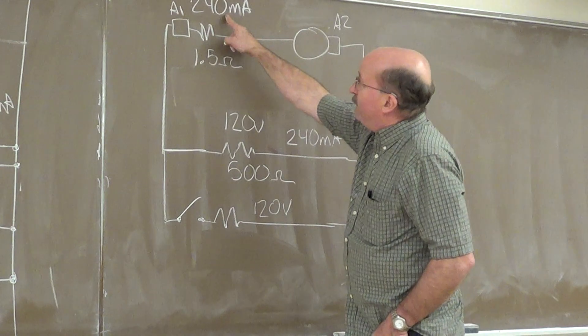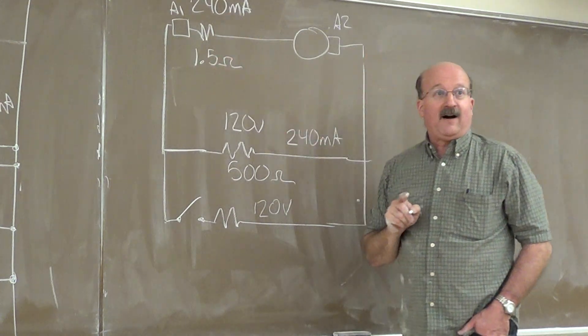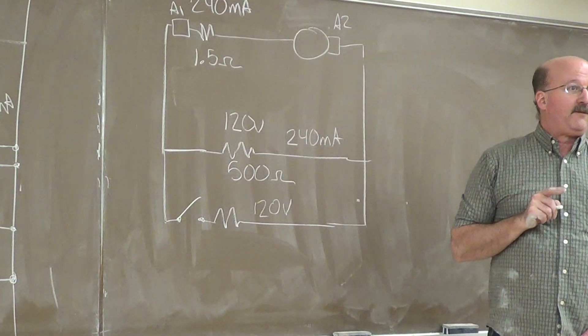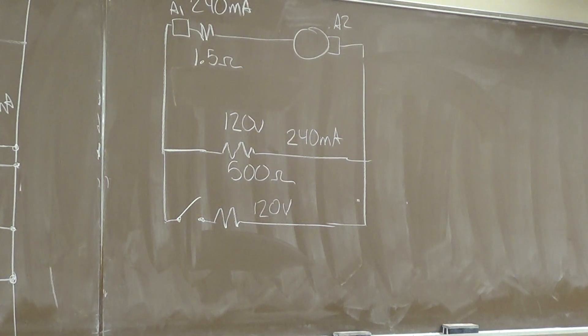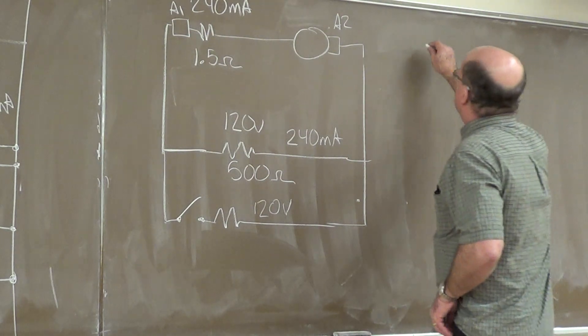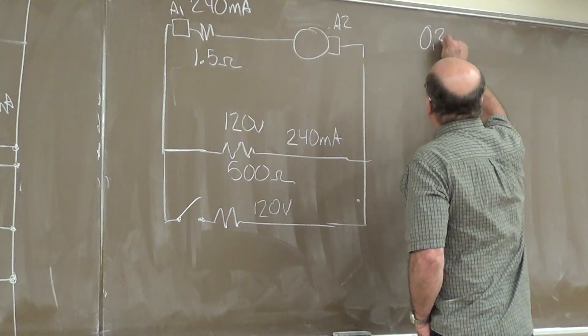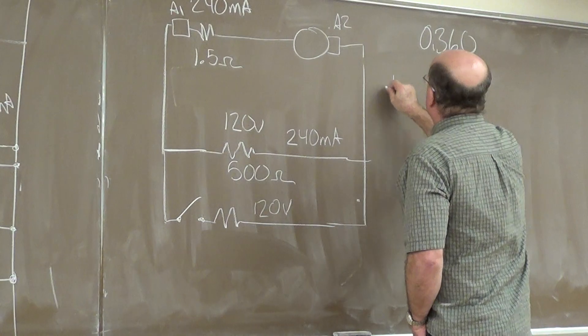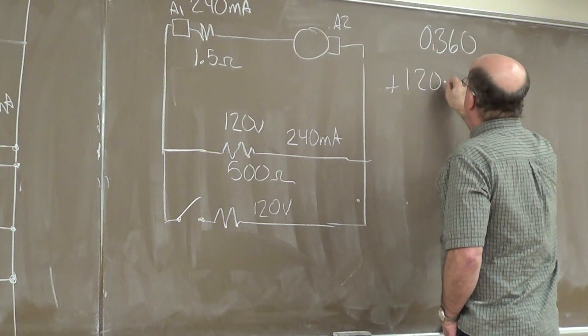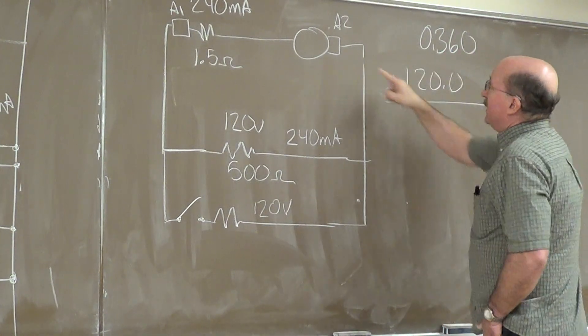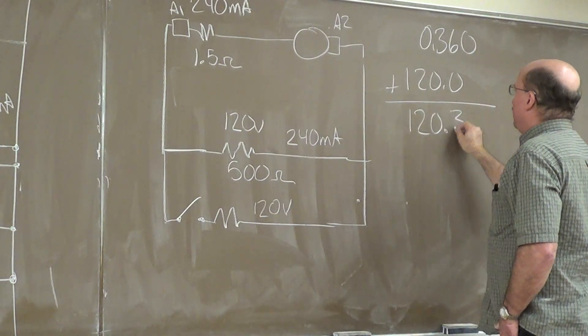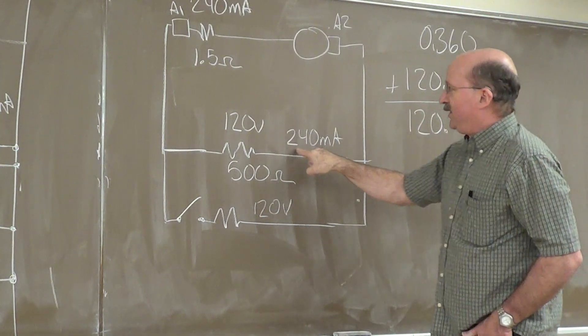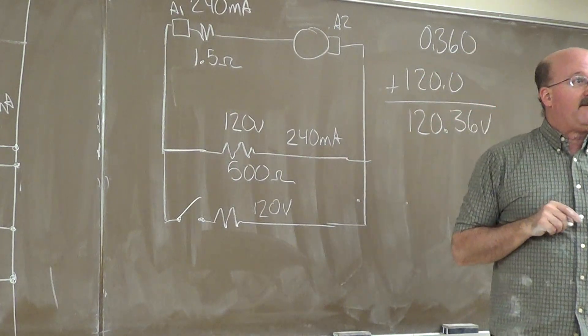We know we have 240 milliamps times 1.5 ohms. What is that voltage? 360 millivolts. 360 millivolts. Plus our 120. That means this generator is generating 120.36 volts in order to get us 120 volts output.